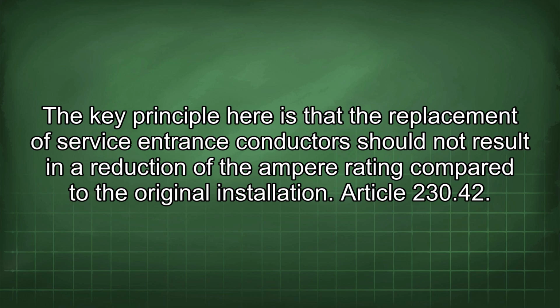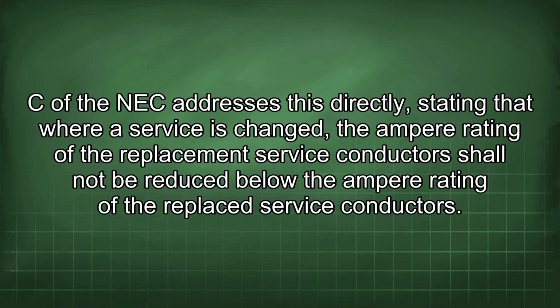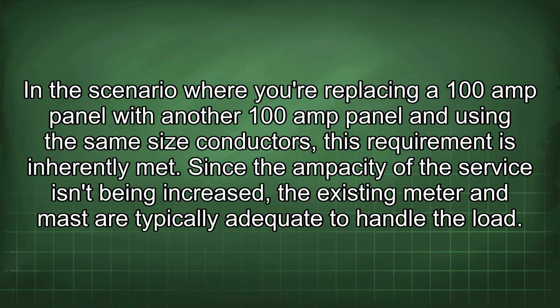Article 230.42(C) of the NEC addresses this directly, stating that where service is changed, the ampere rating of the replacement service conductor shall not be reduced below the ampere rating of the replaced service conductors. In the scenario where you're replacing a 100 amp panel with another 100 amp panel and using the same size conductors, this requirement is met.